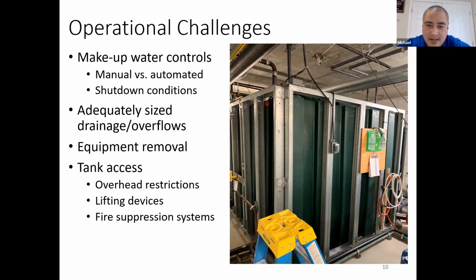So equipment removal and tank access is paramount in these situations. When we're on top of a tank, like in this picture, we have a pulley system which will pull out our gray water pump, well in excess of about 100 pounds, and use that to pull the tank out and pull the pump out. However, when working on top of a tank, we'd notice overhead piping and fire suppression systems. Operators know you don't want to bump or get near a fire suppression system, because if you set it off, it's going to be a much bigger deal than just changing the pump.